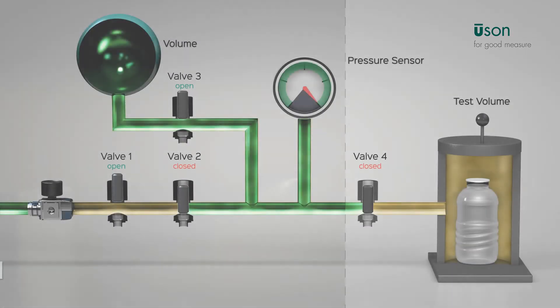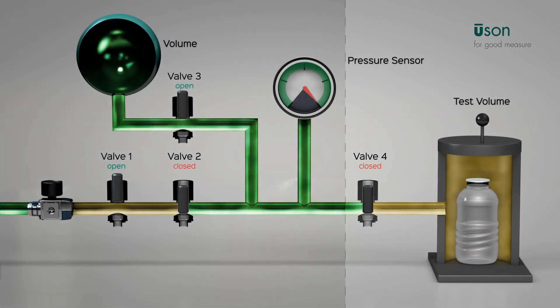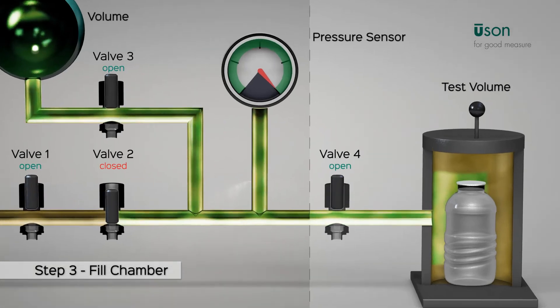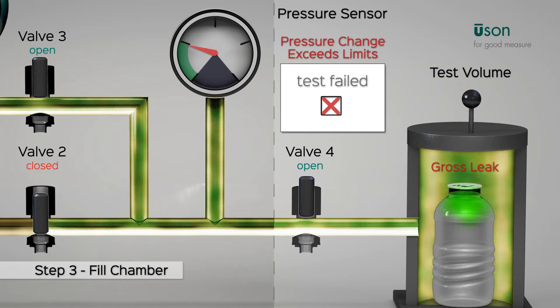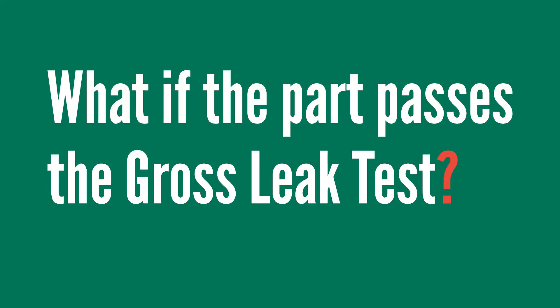If there's a drop in pressure during the measure step that is below acceptable limits, this means the test part is filling with air and there's a gross leak. But what happens if the part passes a gross leak test? You might think this means we have a good part — not necessarily.